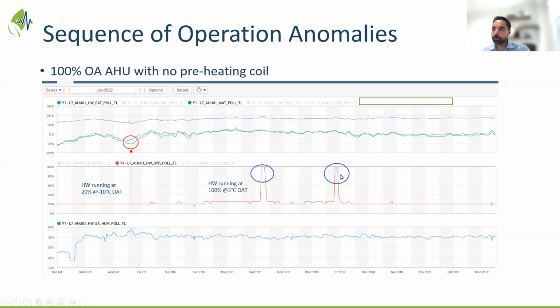went to 100% for no reason, even though obviously there's a reason in the programming code which led this to run to 100%. But if you look at it, at minus 10 degrees C you only need 20% of the wheel running to satisfy your supply temperatures, whereas when it's around 2 or 3 degrees C outside, the wheel went to 100%. So it's counterintuitive that you only need 20% wheel at minus 10, yet you need 100% wheel at 2 or 3 degrees C.